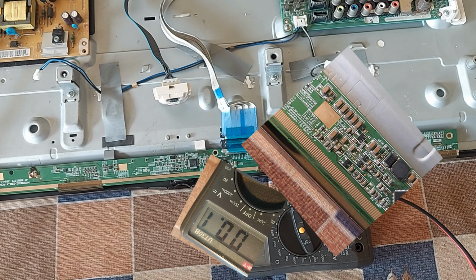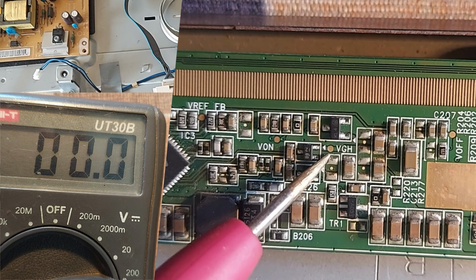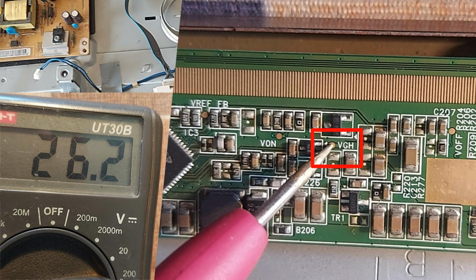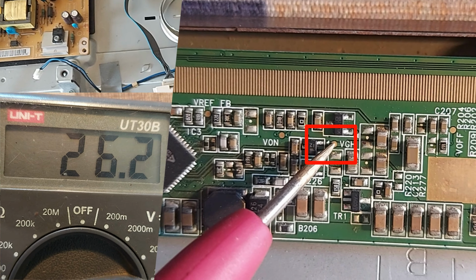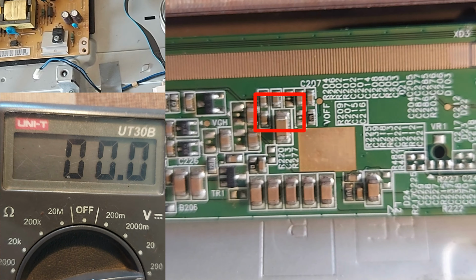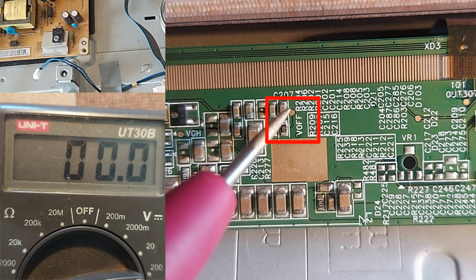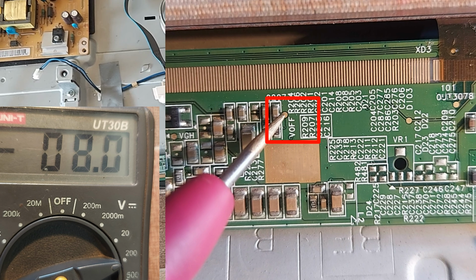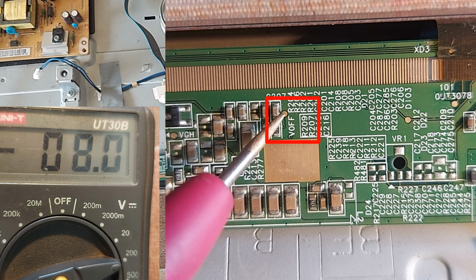Now according to the symptom, we will only measure the VGH and VGL voltages. VGH about 26 volts. Okay. Then VGL or VGOF, VGL minus 8 volts, okay.